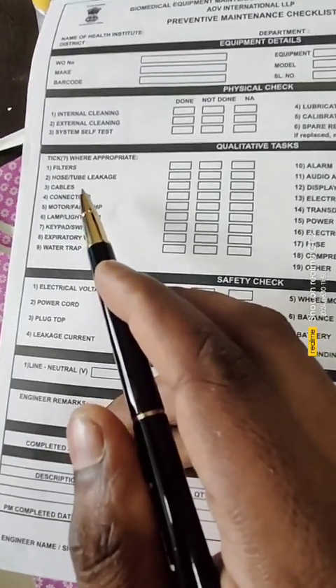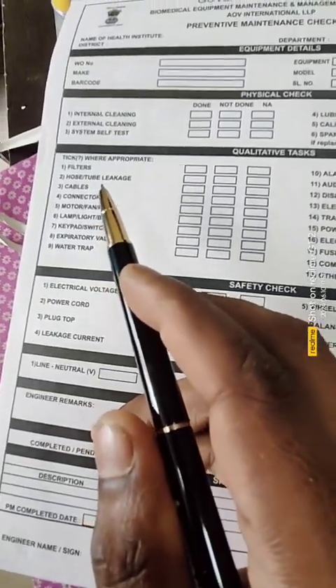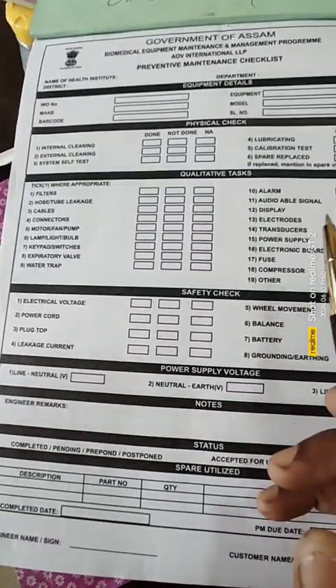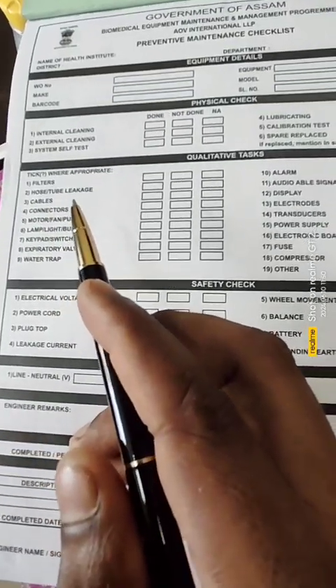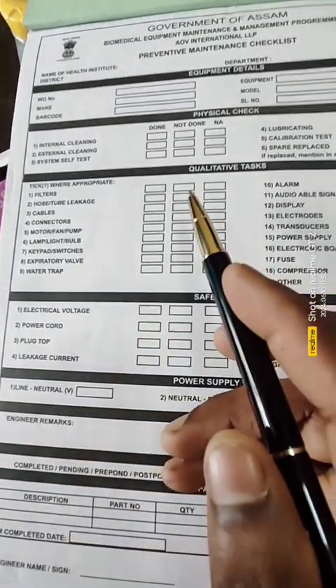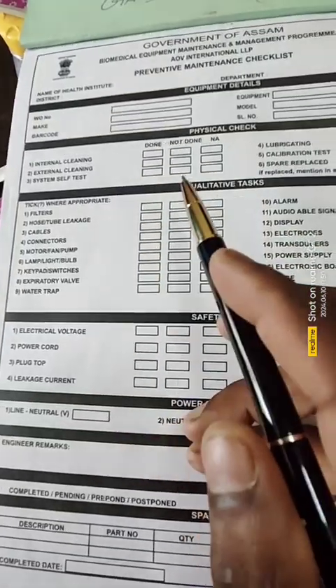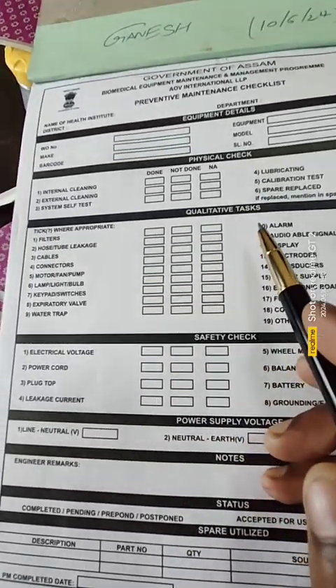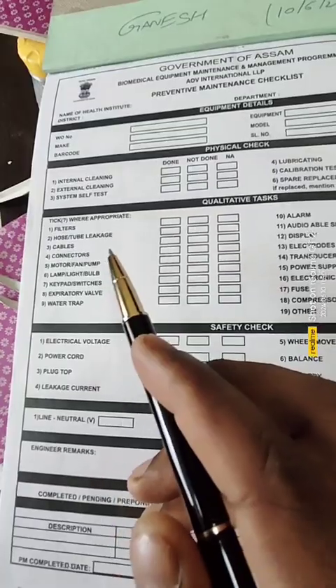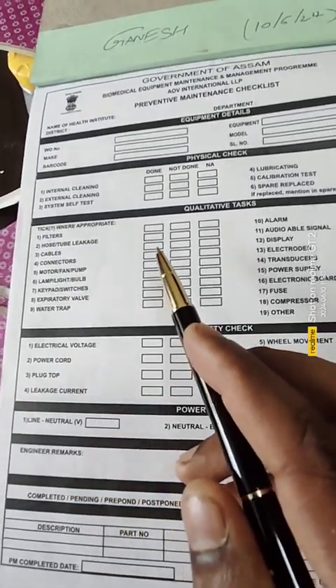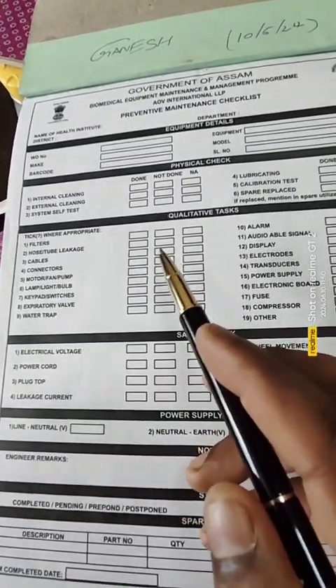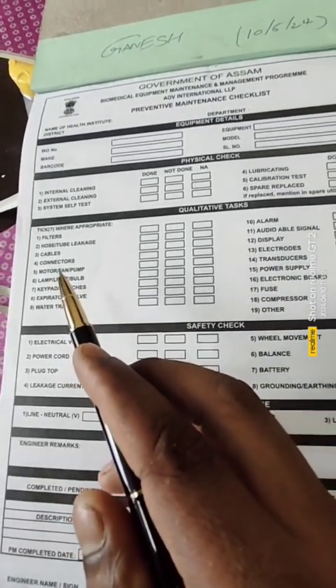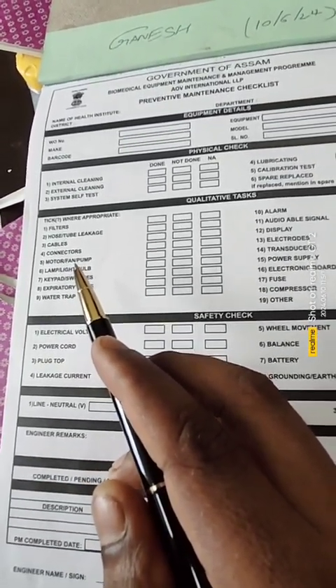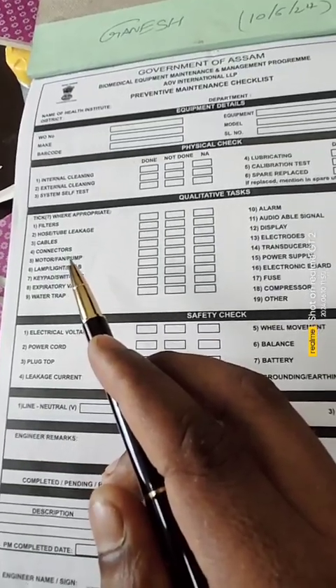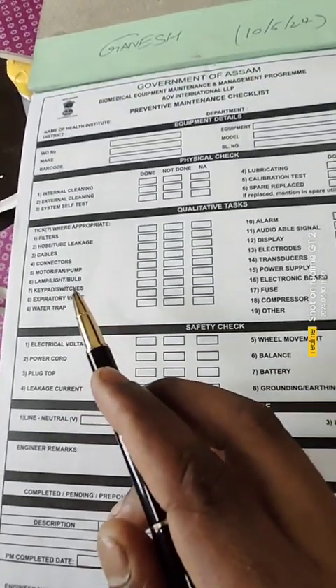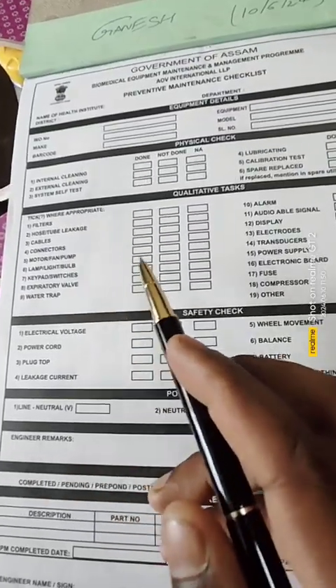Okay, listen carefully, friends, my dear team engineers. Filters, for example, we take a patient monitor. In the patient monitor, filters are available or not, so we have to think yes or no. Then you have to check it: done if available, not done if not available. Okay, next, hose tube leakage. Hose tube leakage also, available or not, just analyze once. Yes, because NIBP is available. Next, cables, power cables, connectors. Next, knob connectors and NIBP connectors and IBP connectors, and whatever is available, otherwise not done. Motor pump, the NIBP motor pump is available in the patient monitor, so you have to mark done.